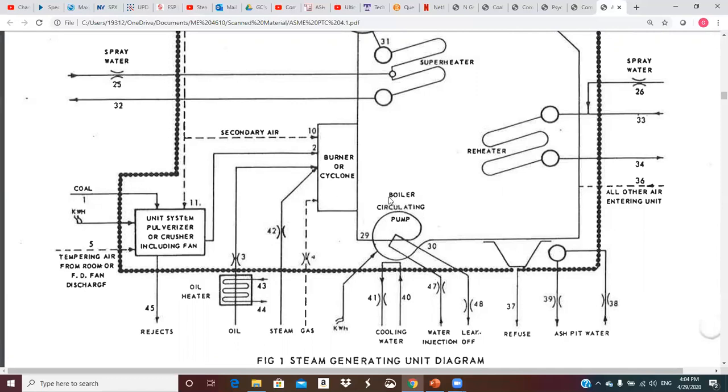So we have our burners in here. If we have a forced draft or forced circulation boiler, this would be the circulating pump that's providing the circulation around the water loop. And so it's inside. And we have electricity going to that. And so that electricity has to be quantified. A lot of times there are some cooling water associated with the walls of the boiler, certain locations to make sure that things don't overheat, just for protective purposes. So we could have a water flow that's coming in here at 40 at one temperature, coming out at 41, picking up some heat.